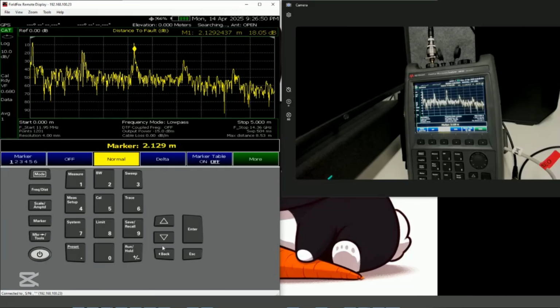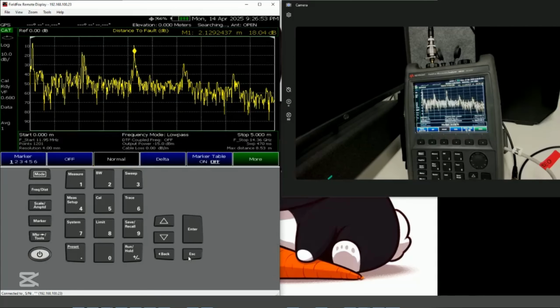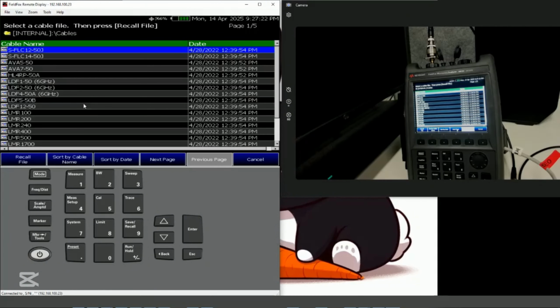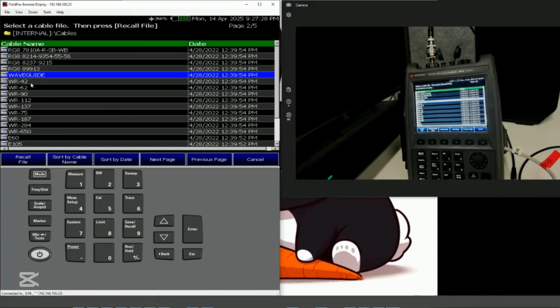So the next thing I want to show you is how to get the velocity factor if you know the cable property, for example, you get RG58 from a third party to build this type of BNC cable. So you can actually go to measure, setup, DTF cable specification, edit recall cable. So you can edit a cable, you can build a new cable property, then you can save the cable or you can recall the cable. So we're going straight with recall cable. So we have a long list of cables that's available in the market, and you can actually recall the type of cable that you are using.